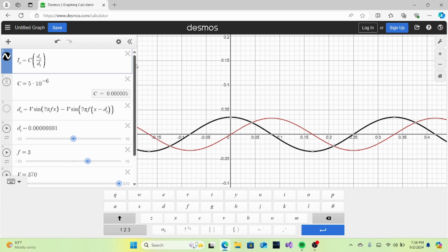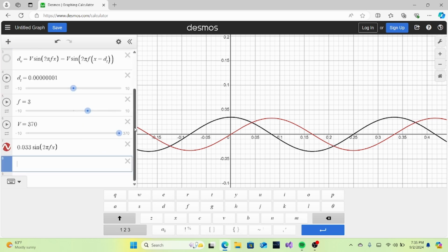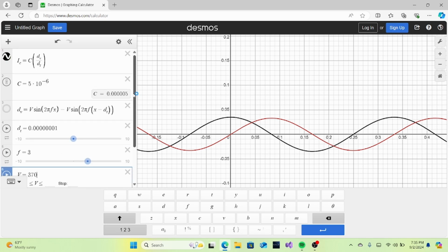When I'm working, most of the capacitors that I'm troubleshooting are capacitors that are being used to create a phase change for a motor. So generally IC here is equal to the start winding current of the motor that the capacitor is attached to. So you can measure start winding current and divide it by dV over dt. And in order to find dV over dt, I just do something like we described above. I look at the voltage over the capacitor, or across it, and if it's 370 volts, then we can solve here. I'll actually demonstrate this for you.